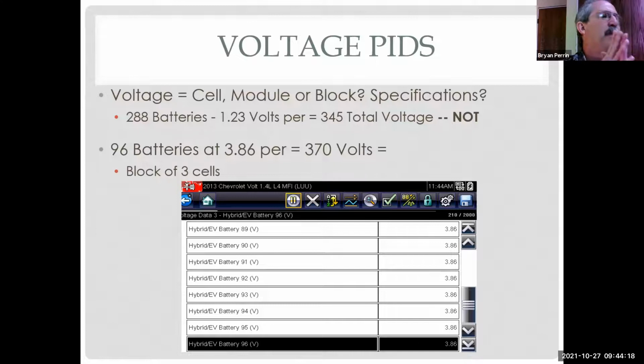As a rule, we say normally plus or minus 10%. Some manufacturers are stricter, some looser, but it's a good rule of thumb. 10% of 3.86 would be a 386 millivolt difference. If I have a battery system that works on 14.4 volts, 10% is 1.4 volts. So you can see 10% is a good rule of thumb. We shouldn't get concentrated on whether 400 millivolts or 300 millivolts is okay. We're looking for what's not the same, and the higher voltage the system uses, the bigger the spread in total numbers that's acceptable, because it's all about percentage.